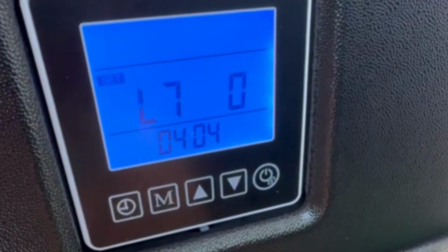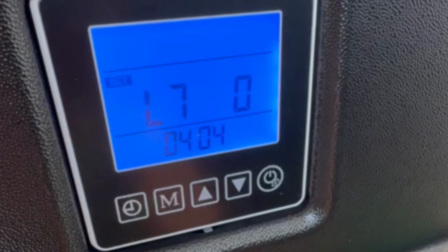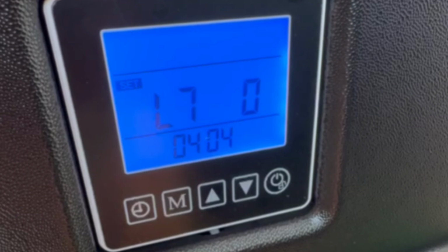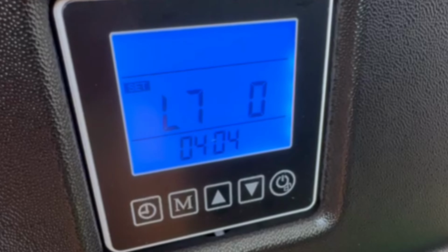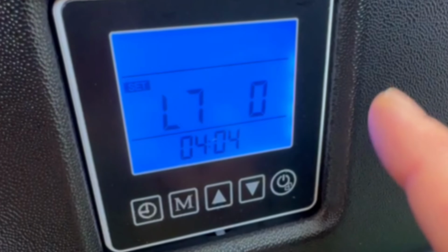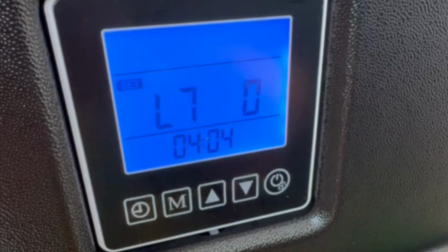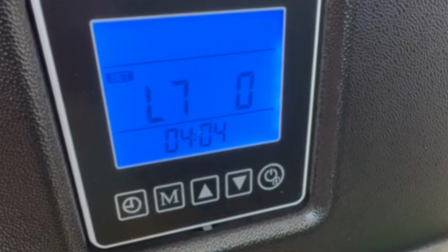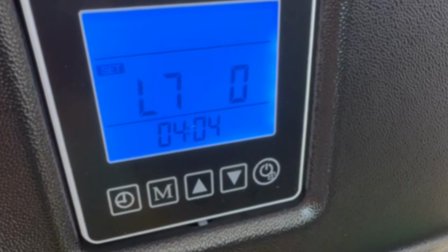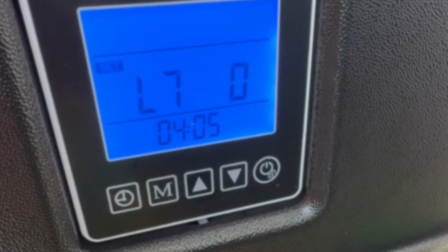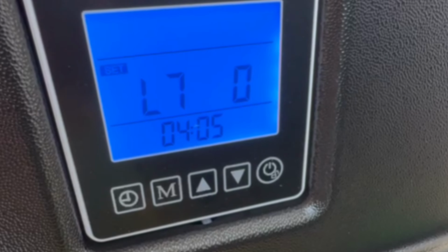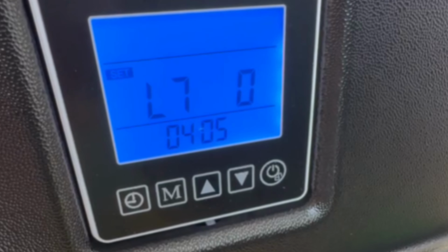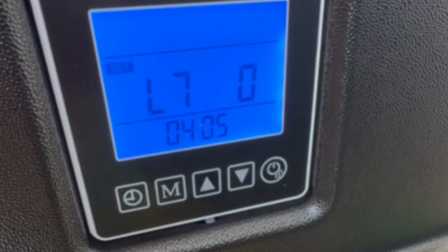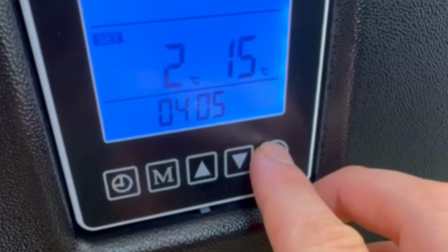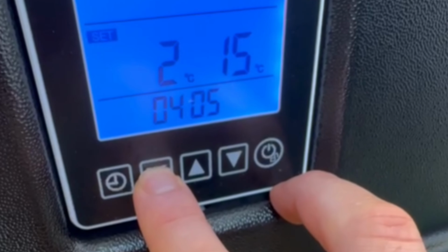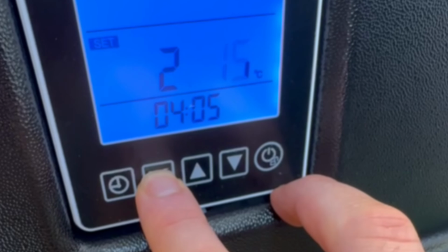0 means that the pump or the UV, if wired into P1 and P2 on the circuit board in the chiller, will stay on after the fan goes off. So when the chiller reaches temperature, the fan will go off, but the pump or the UV, or the pump and the UV, won't go off.